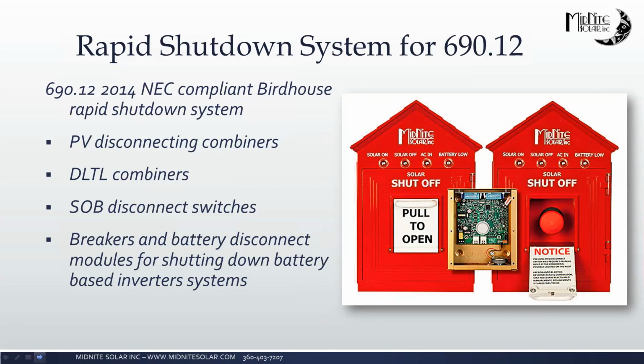The birdhouse gives you 100% positive feedback. I think it's maybe one of the only rapid shutdown solutions on the market that will give you positive feedback. It will actually let you know through the cable that all the switches have opened and it is physically safe to touch. The birdhouse will also interconnect with an alarm system, so a fire alarm trigger could shut the birdhouse down, or vice versa. If the birdhouse is triggered, it could notify the fire alarm system so you get notification the system has been triggered.